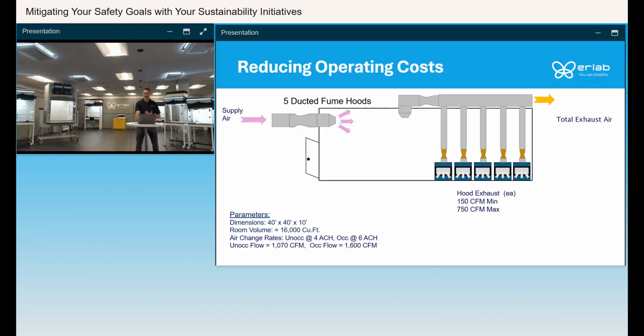So now I want to talk about these high-density fume hood labs. How do you reduce your operating costs? If you look at this slide, this is going to be a 40 by 40 lab, so 16,000 cubic feet with 5 ducted fume hoods. Typically what we see most of the time, the hazard risk analysis will keep the required minimum air changes to 6 occupied, 4 unoccupied. So if you design this lab with 5 ducted fume hoods, even if they're VAV, variable air volume hoods, you're going to have to design it for worst case scenario.